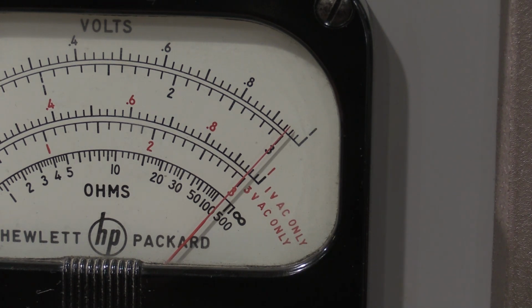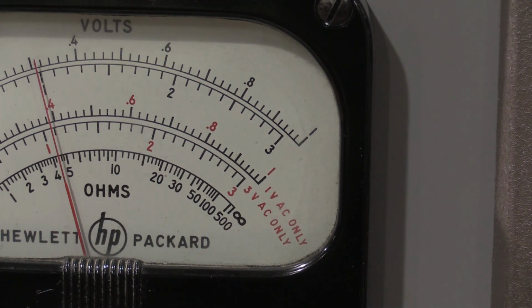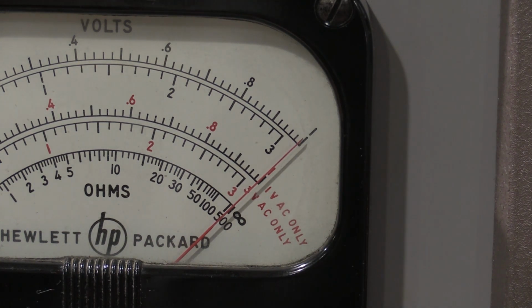So just because, let's check the 10 and 30. Now, there are no calibrations for these. It's just the resistor ratio stability, or ratio in the divider, to make the scales line up. So we're going to go down to 1. We're going to go down to 0, kick it up to the 100 volt scale, because that then puts us at 10. And we are at 10.00237 on the 7510, and we are very, very much right on the one.